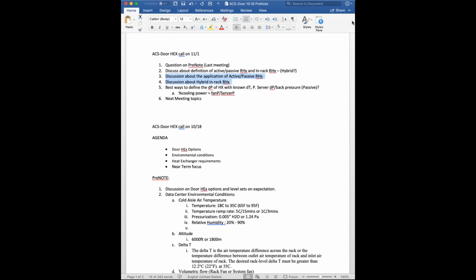For them, it was really kind of a two-point conversation. One, they were having a very high heat load running their supercomputer, and two, they didn't want to add a large burden onto their existing infrastructure for air handling units, but they already had a large amount of chilled water they could utilize. So it was kind of a win-win in most regards.